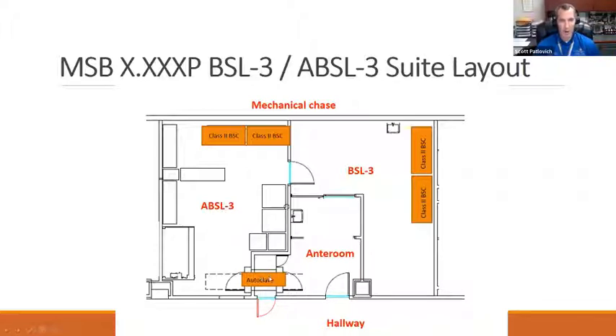And then there's a pass-through autoclave built into the facility. So all of the dirty contaminated waste goes out of the facility through the autoclave, everything gets decontaminated and then brought out on the clean side, which is inside the anteroom, after a validated cycle is completed through that autoclave. So that's pretty simple how this works. In the back is a mechanical chase where the HVAC system is located and other services, electricity, plumbing, et cetera, for the facility. Highlighted in yellow are 2 hands-free sinks that can be operated by a foot pedal, in the anteroom and inside the laboratory itself.